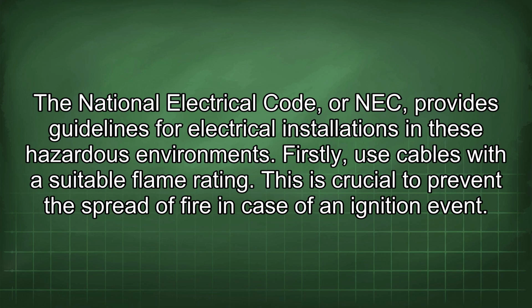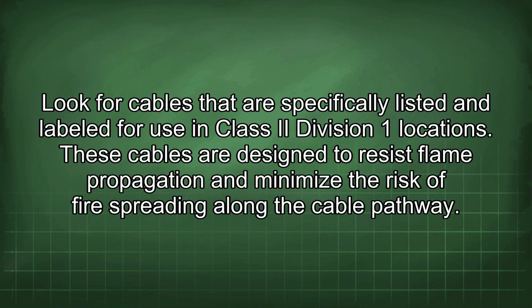Firstly, use cables with a suitable flame rating. This is crucial to prevent the spread of fire in case of an ignition event. Look for cables that are specifically listed and labeled for use in Class Roman 2 Division 1 locations. These cables are designed to resist flame propagation and minimize the risk of fire spreading along the cable pathway.